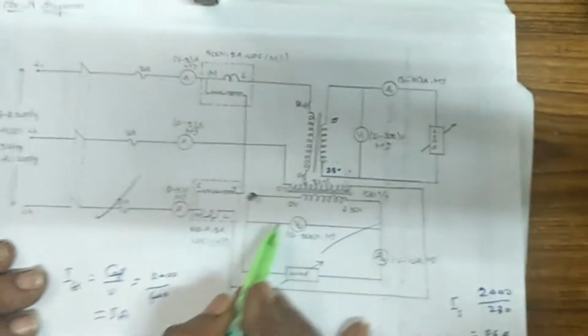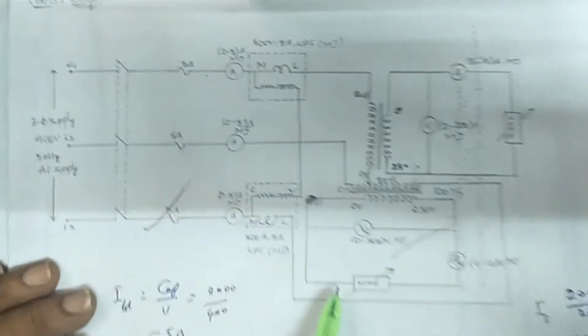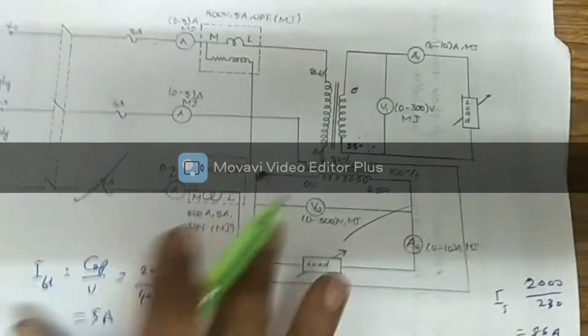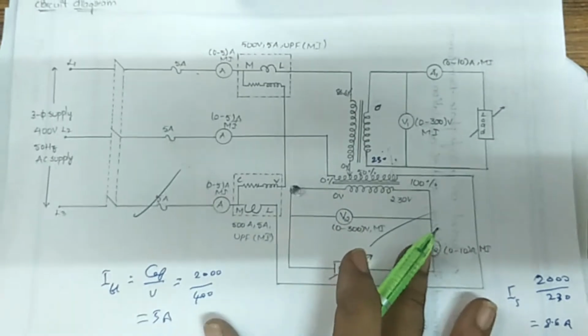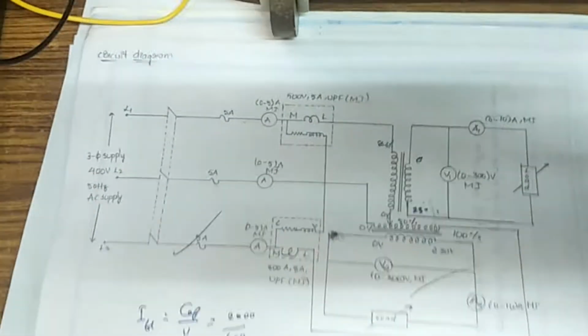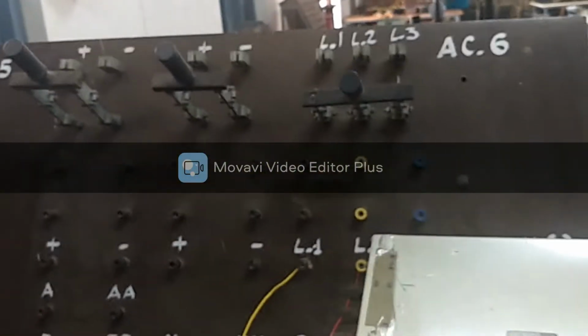Similarly, the voltmeter and ammeter rating on the other side, that is the secondary of the main transformer, is also the same, 0 to 300 and 0 to 10 amperes. After deciding the ratings of ammeters, wattmeters as well as voltmeters, then we go for the connections of the Scott connection of transformer. So here, these are the input terminals. See here, this is input terminal L1, L2 and L3.